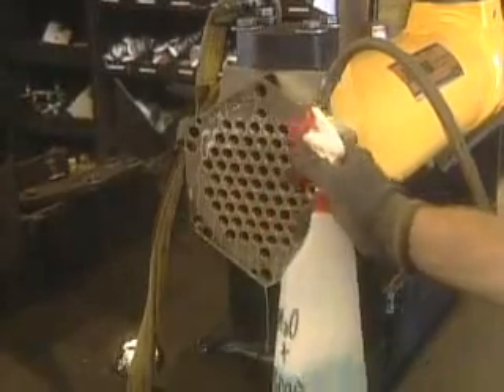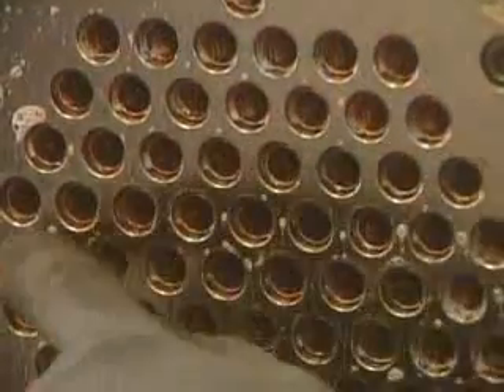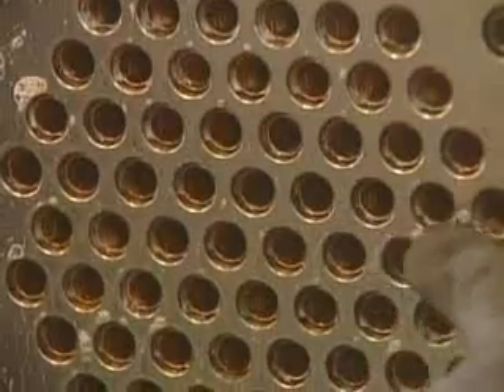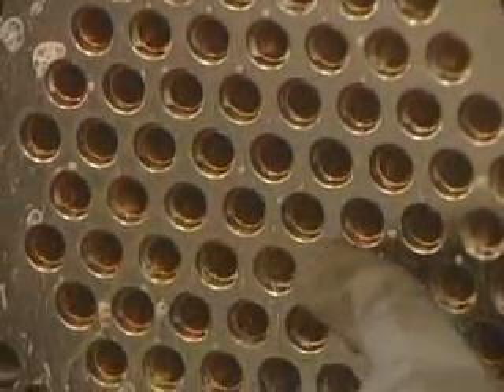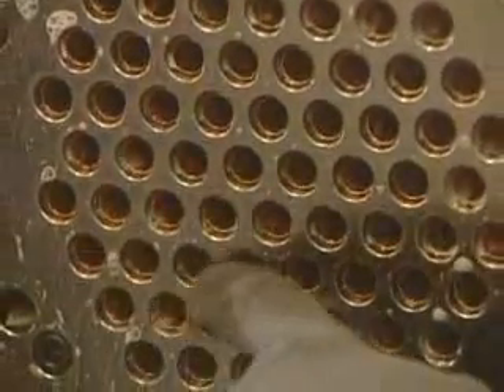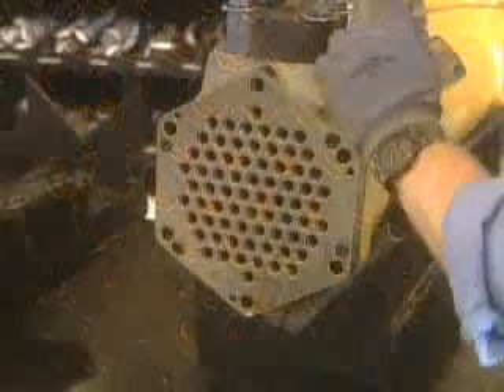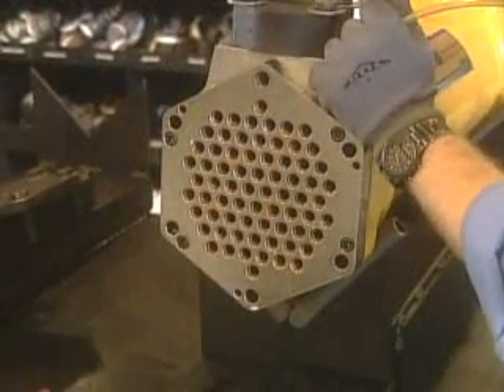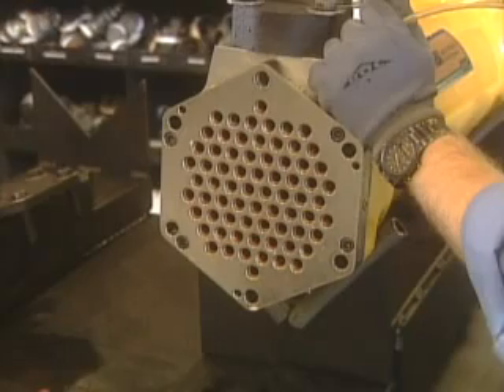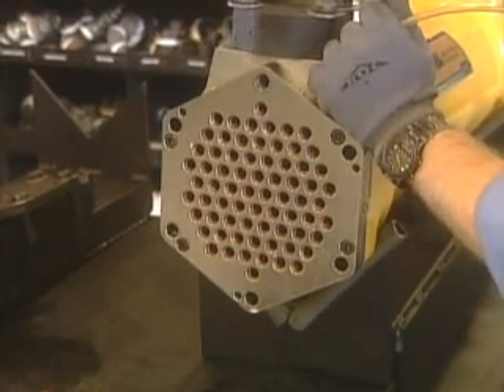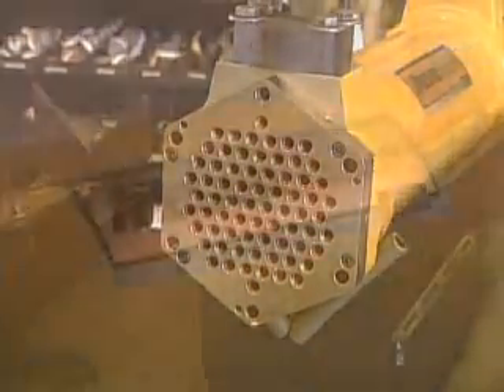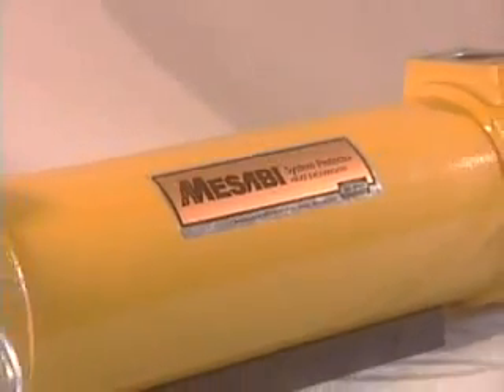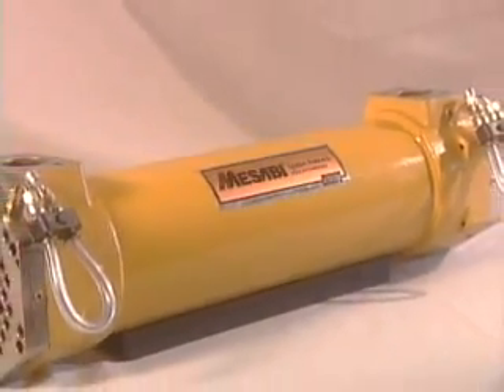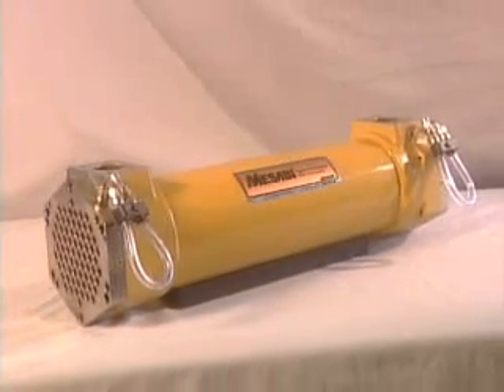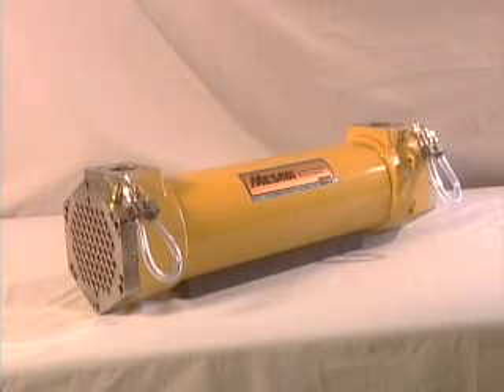Repair as required. After any repair, restart the test sequence at step 1 and continue until the sequence of pressure cycle tests has been completed. Remember to dry the detection chamber after testing. Dry it from the sight tube detection port by removing the plug opposite the sight tube. This completes the procedure for disassembly, reassembly, and testing of the Mesabi System Protector Tube and Shell Cooler.